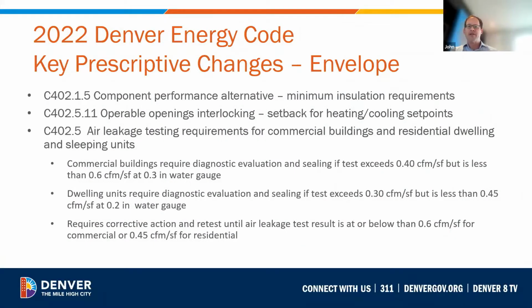A lower fenestration U factor is required for a new category designated as all other fenestration. This required U factor of 0.30 is slightly more stringent than other classifications of windows, and it would apply to windows such as architectural windows. While interlocks are required for operable windows to set back heating and cooling set points when windows are open, projects that use evaporative cooling may still have the cooling system enabled when windows are open. That's just a minor clarification applicable to Denver in its dry climate.